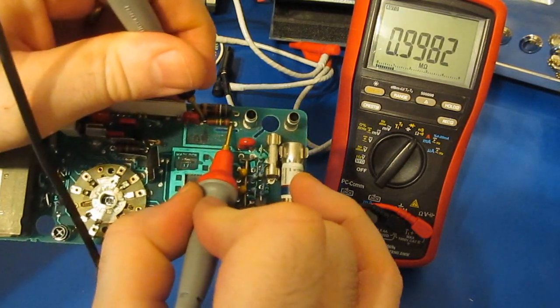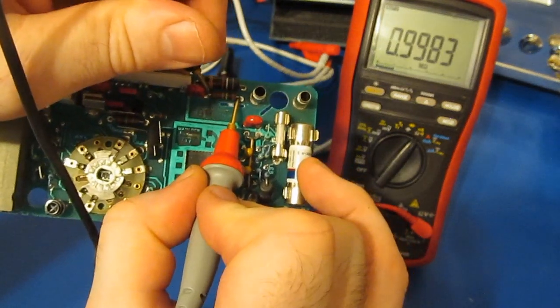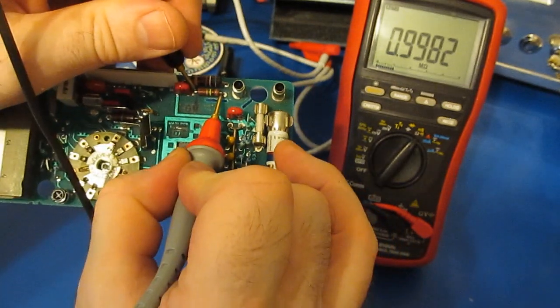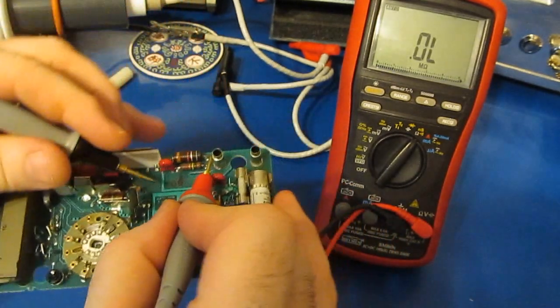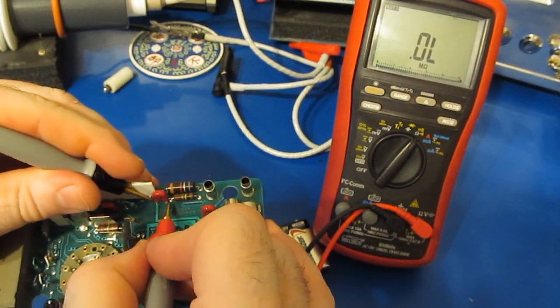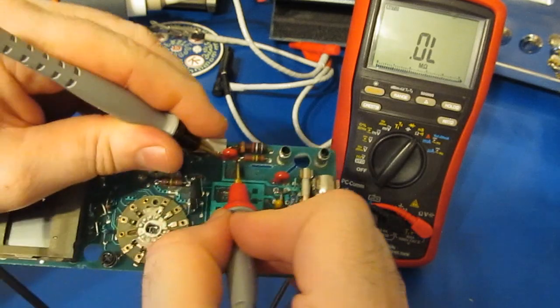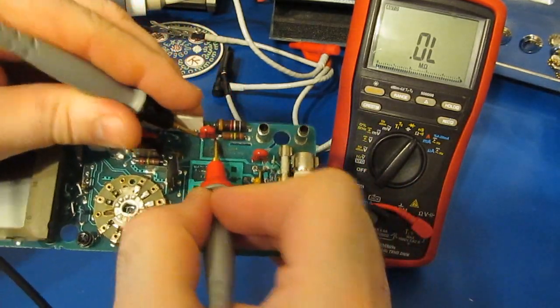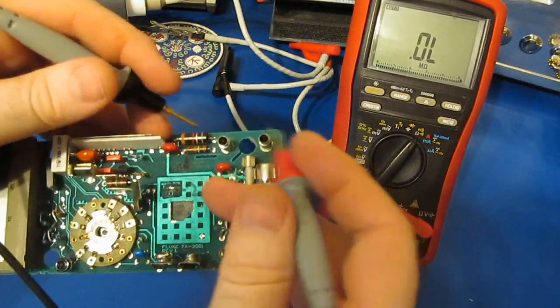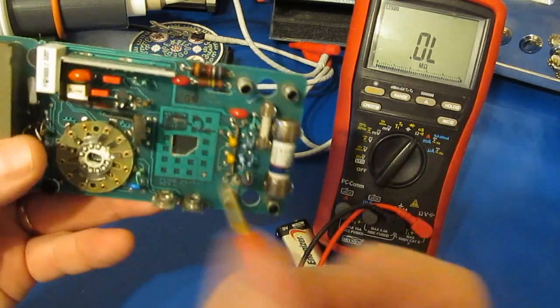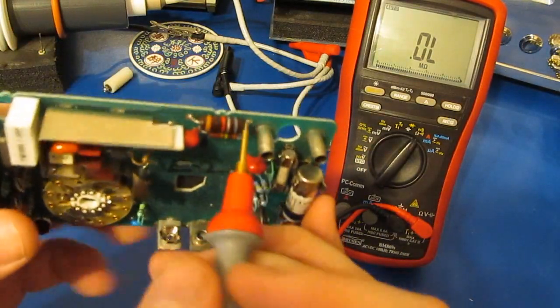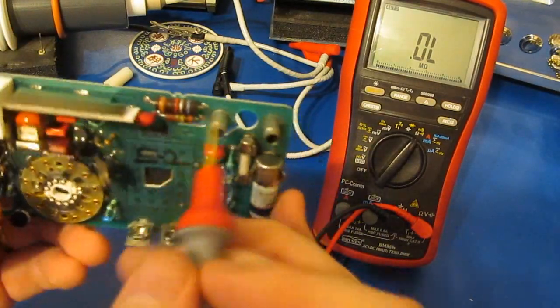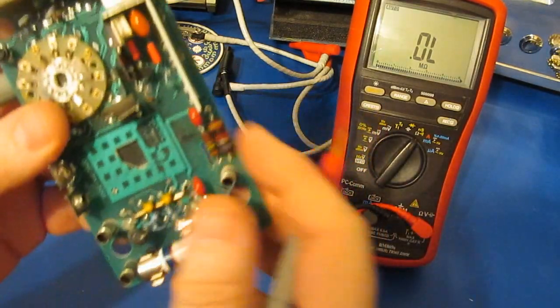Again, these meters have essentially a fusible resistor and it looks like that particular one has opened up. This should be our one meg - yep, let's see, that's just fine. And let's just look at our other spark gap real quick. Of course that one has not been arcing - see that one's fine as well. So yeah, basically what's happened here is we damaged this resistor. This would have to be replaced.